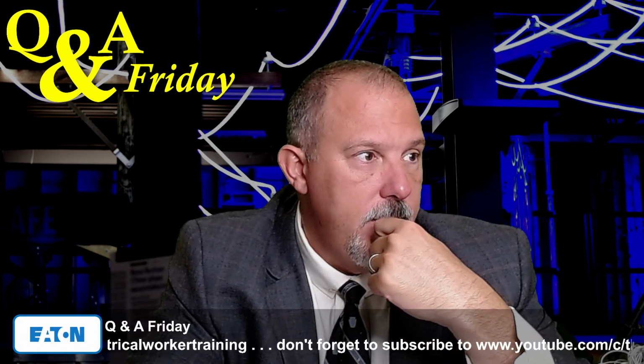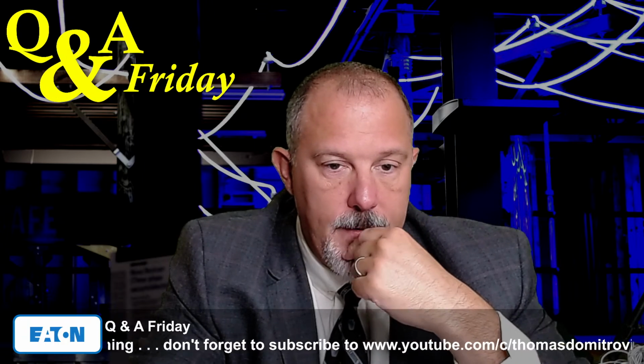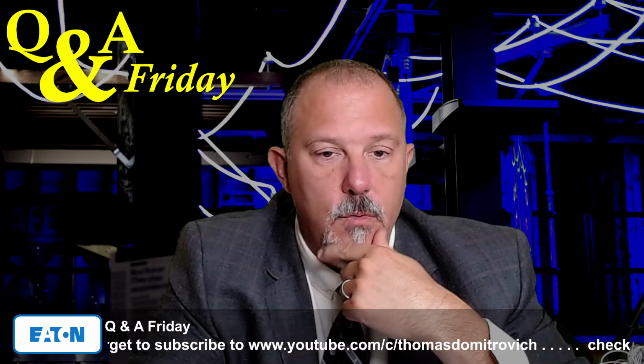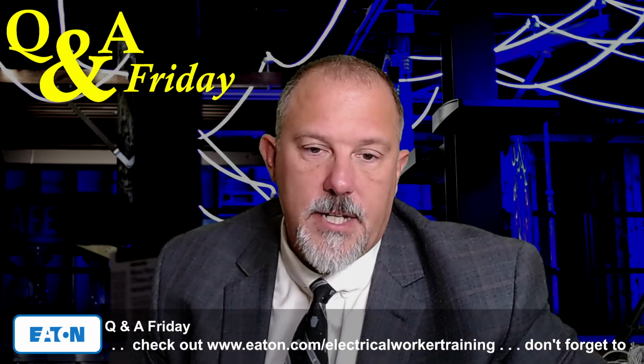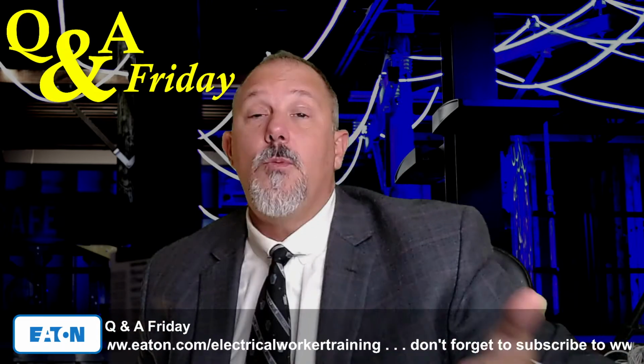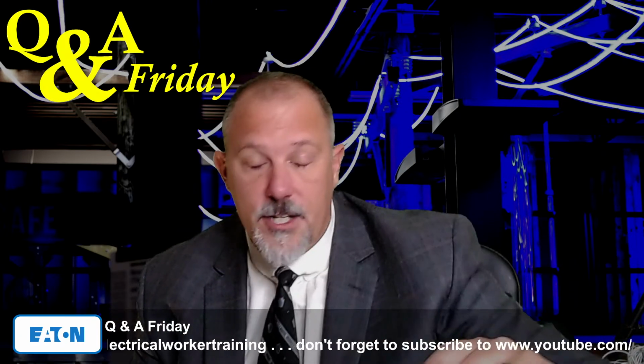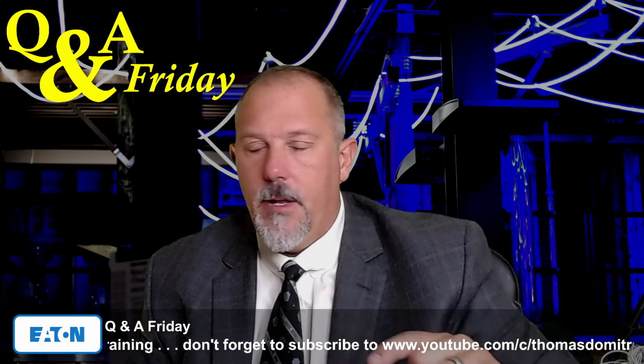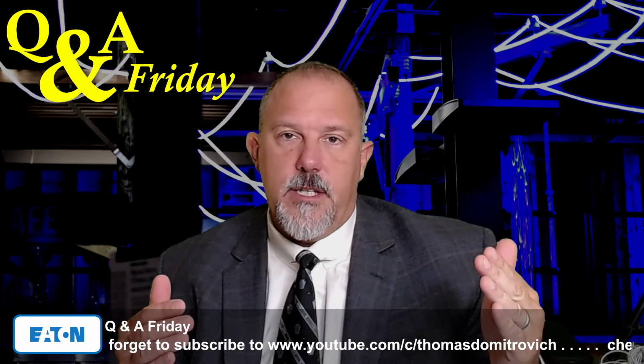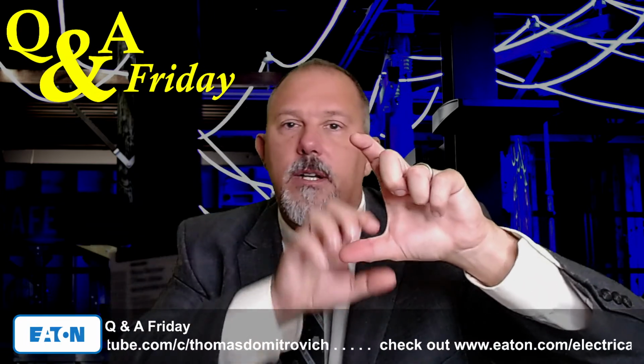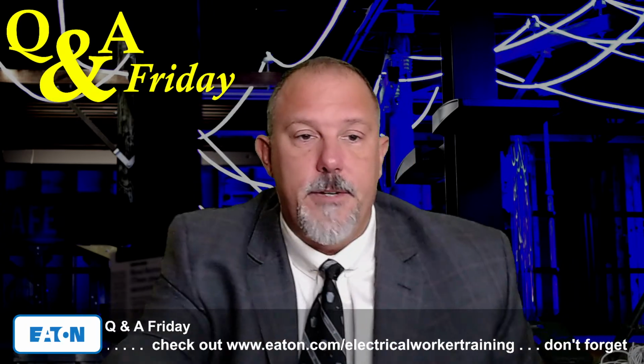So what your question was, your question said, in the graphics you have shown where motor fault current contribution affects adjacent circuit breakers fault current, I don't see how 240 is written properly to address. Instead, it seems to be written to address only the series rated pair at a given motor or motors connected in the middle of a series rated pair. And that's the way it's supposed to be written. So your interpretation of it is actually accurate. And hopefully I conveyed that. You're worried about two devices in series, two breakers in series, or a fuse upstream of a breaker and motor contribution in between because the downstream circuit breaker is going to see more current than how we test it as a series.